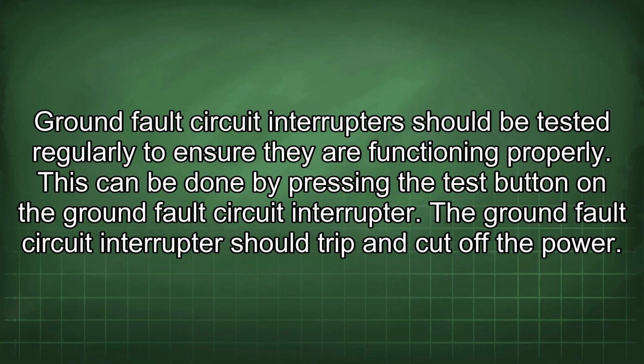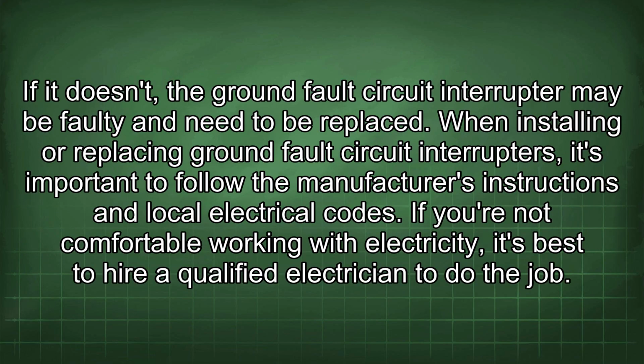Ground fault circuit interrupters should be tested regularly to ensure they are functioning properly. This can be done by pressing the test button on the ground fault circuit interrupter. The ground fault circuit interrupter should trip and cut off the power. If it doesn't, the ground fault circuit interrupter may be faulty and need to be replaced. When installing or replacing ground fault circuit interrupters, it's important to follow the manufacturer's instructions and local electrical codes. If you're not comfortable working with electricity, it's best to hire a qualified electrician to do the job.